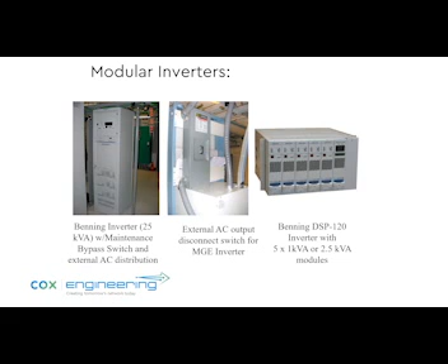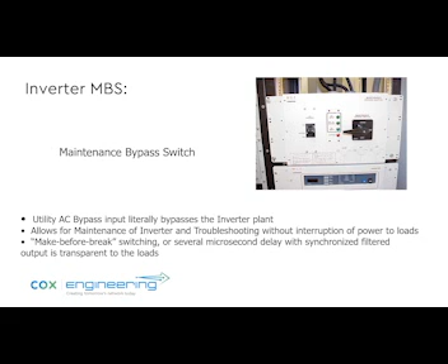So here's some pictures of modular inverters. Typically, they're going to have a disconnect switch, like a maintenance bypass switch, much as a UPS would. And really, a UPS is simply a big box which has a rectifier, an inverter, and batteries in it, taking these elements we're talking about and chunking them all together. So the inverter maintenance bypass switch is there in case you need to work on the inverter plant itself.